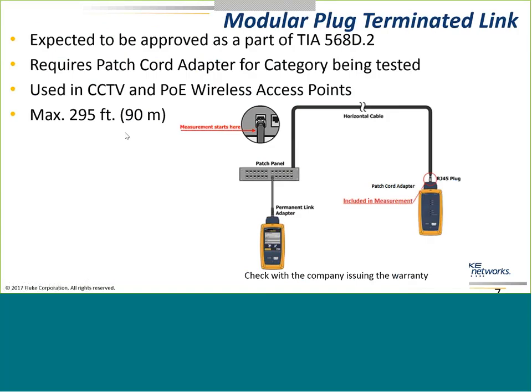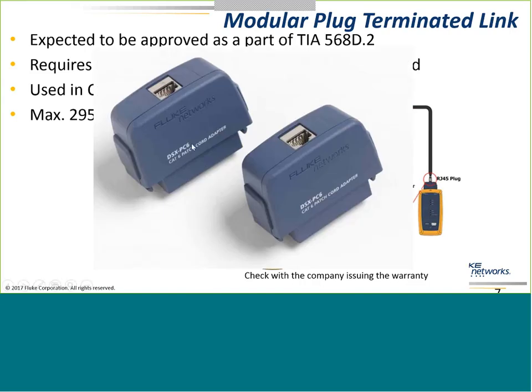We've seen the writing on the wall that in the next revision of the ANSI/TIA-568 standard, they're going to incorporate this modular plug terminated link. We'll have a permanent link adapter on one end. On the far side, something special — we're not going to use a regular channel adapter, we're going to use a patch cord adapter. If we used a channel adapter, we would not include the mated NEXT from this connection. In order to include the mated NEXT and measure the termination of the plug, we're going to use the special patch cord adapters.